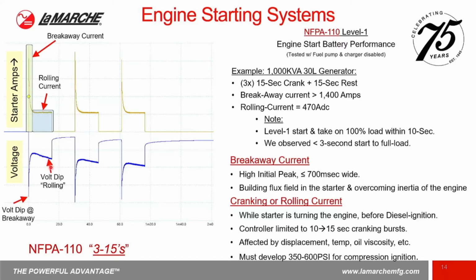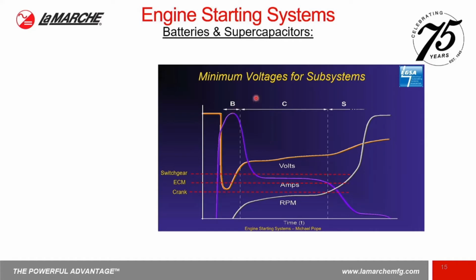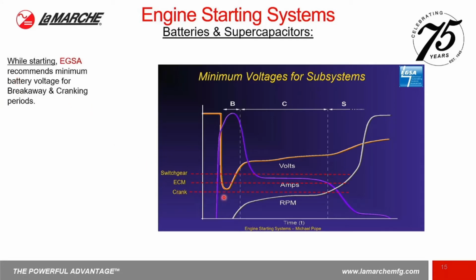You'll notice there's a voltage dip during the same period of time. Again, the battery voltage is a reflection of the total load current. Here's another view, which comes from the EGSA, and this is while starting. The EGSA has a different recommendation for these periods. For B, the initial breakaway period, on a 24-volt system they want to see the battery voltage stay above 12 volts, even for that momentary dip. During the cranking section, or the rolling current section, the battery must stay above 18 volts. If we're talking about a 12-volt system instead of a 24, then these voltages would be cut in half.